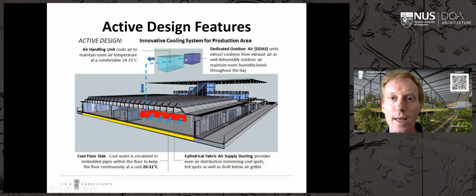After the dedicated outdoor air system, the air that had already been fully dehumidified then went into the normal air handling unit, which would just recirculate air in the factory and ensure the right temperature. The fresh air requirement is quite high in these kinds of factories because various substances go into the air from the production facility, so we followed the ASHRAE figure for required fresh air supply.